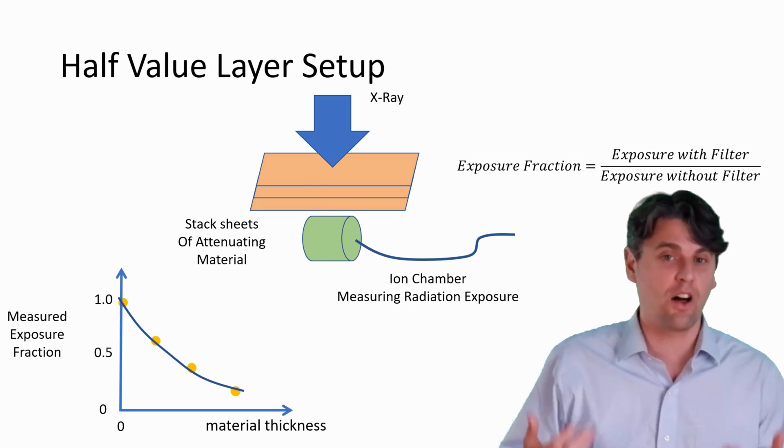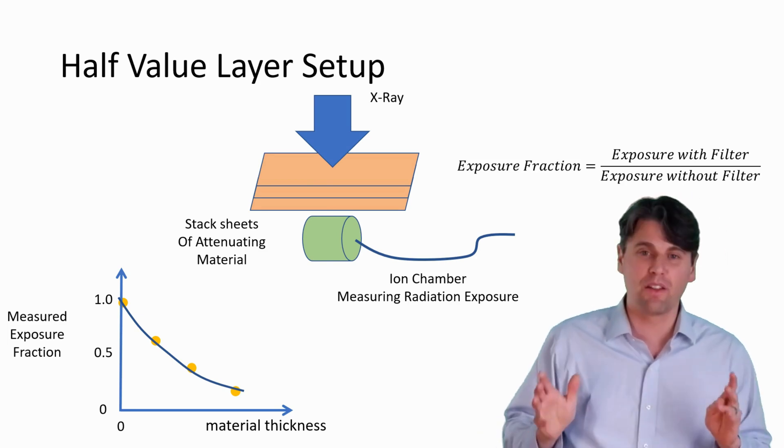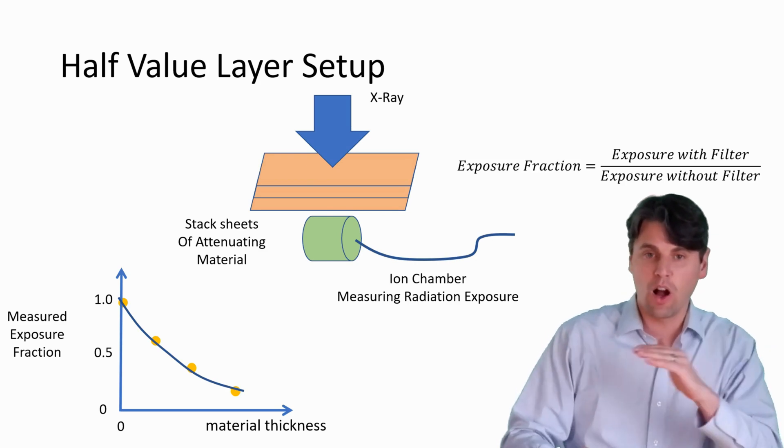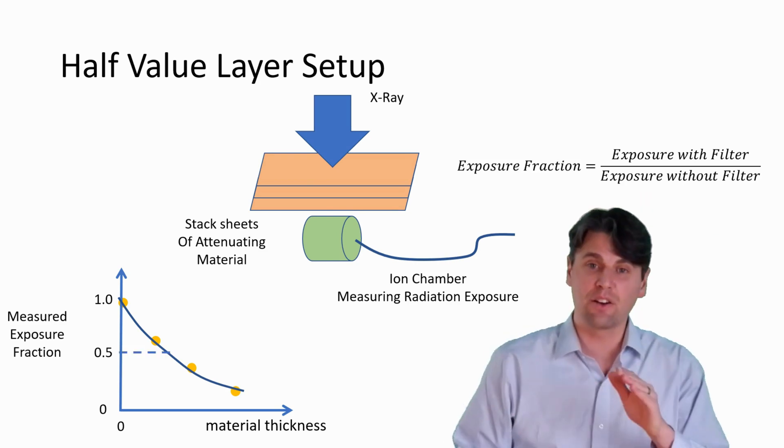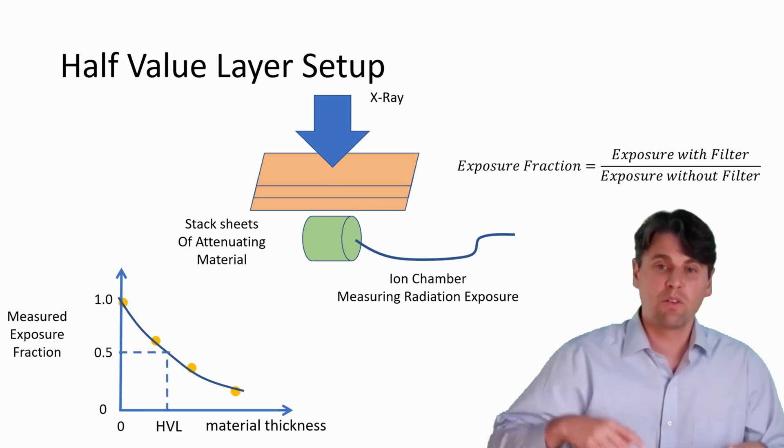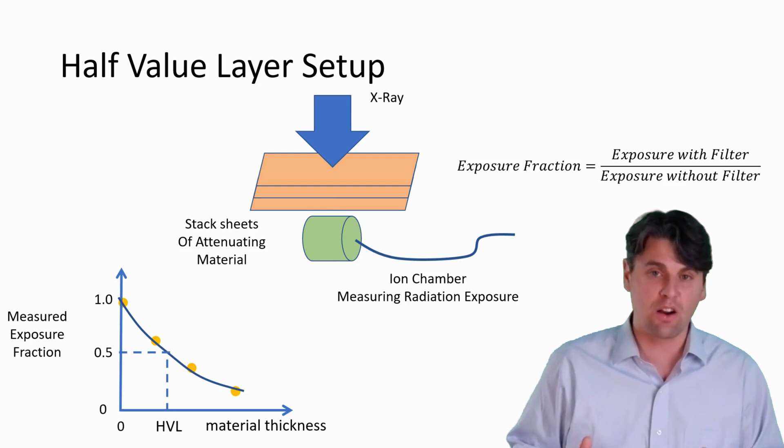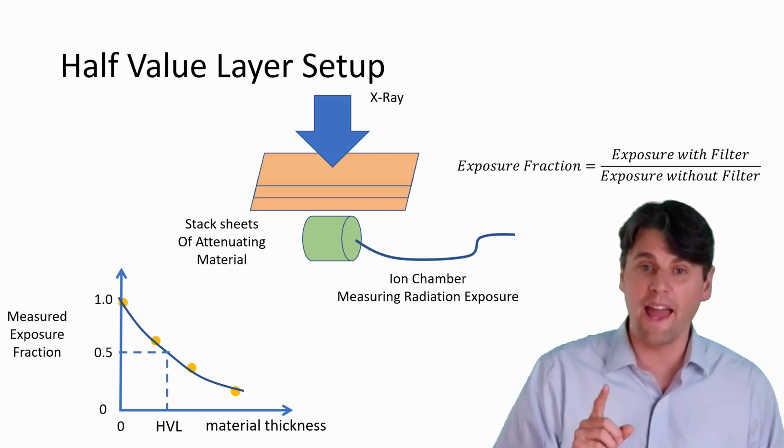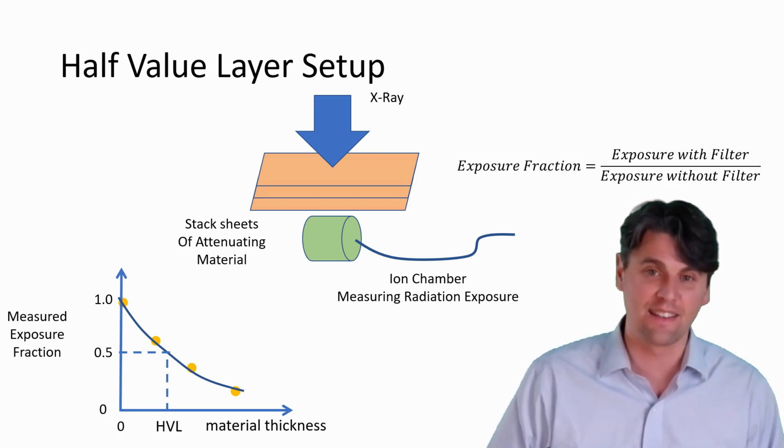We can fit that curve and then we can calculate parameters on that curve. The most popular one is called the half value layer. Go to where the value is one half of the original exposure. We'll draw a line, see where that line intersects our curve, and then we'll draw another line down. Draw that line down, we get what's called the half value layer. So that's the thickness of material that's required to attenuate one half of the x-rays.